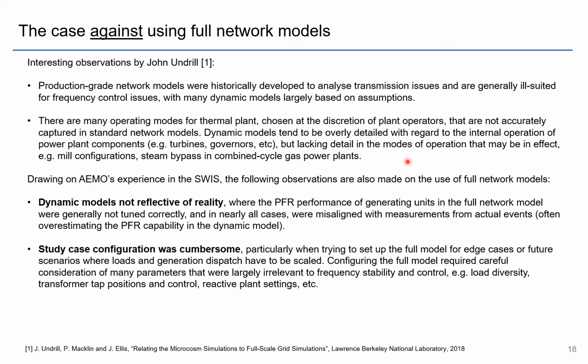The configuration of the study cases was also quite cumbersome. So if you're trying to set up a full model for an edge case or a future scenario where loads and dispatch have to be scaled, then configuring the full model requires real careful consideration of lots of parameters that are actually irrelevant to frequency stability. So looking at different load diversity or transformer tap settings and control and reactive plant settings, and most of them are not all that relevant to the frequency stability analysis at hand.